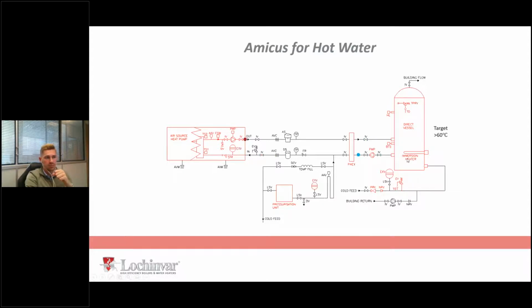The only reason I'm showing this immersion heater, because the heat pump will give you dedicated hot water at 60 degrees centigrade, is that the immersion heater is there for 2 purposes. If it's healthcare, possible you want 70 degrees for an hour a day, the heat pump won't give you that. You need an immersion heater to do your top up if you wanted to do that, if you're not happy to store at 60. Or your heat pump breaks, or it's down for servicing and you don't want the user to be affected.